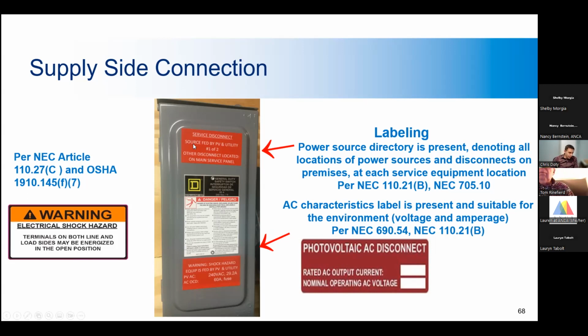And also you want to make sure that there's a plaque or some kind of label showing that there are two potential sources of energy coming into this panel, so that if an electrician comes in later on and needs to shut down the panel, and they shut down the main disconnect but they don't shut down the PV disconnect, that panel is still potentially energized and it could cause shocks.